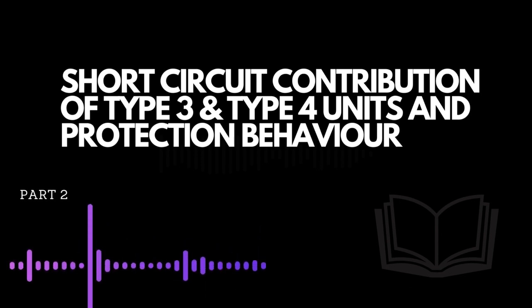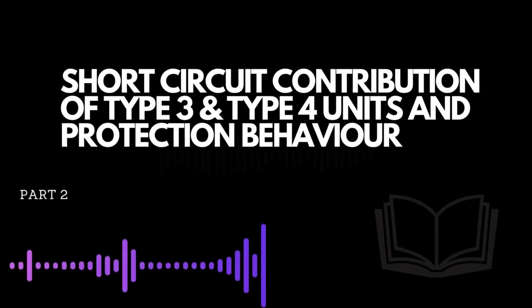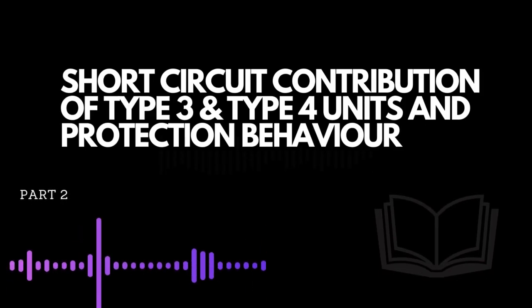Under unbalanced grid conditions, DFIG control is affected by double-frequency oscillating magnitudes. One of the strategies that can be applied to the negative sequence controllers of the converter is to minimize these oscillations in the controls through the decoupling of positive and negative sequence components. Figure 8 shows an example of short-circuit contribution from DFIG under a three-phase fault with a voltage dip of 20% pu on the step-up transformer MV.